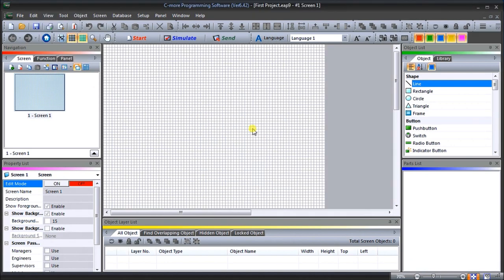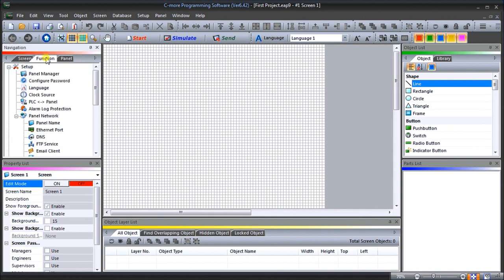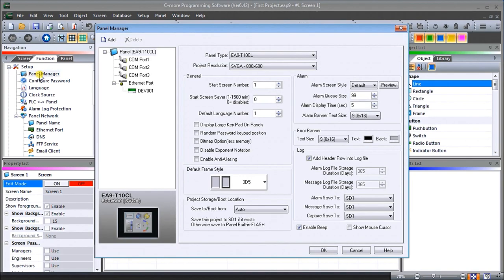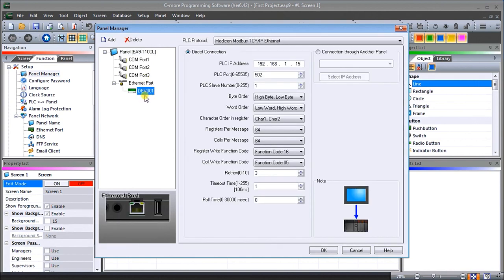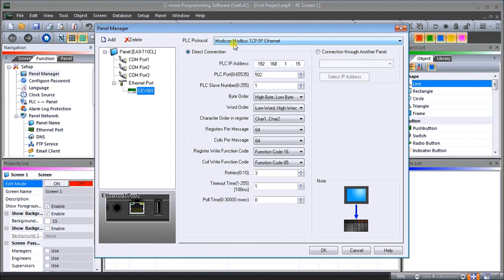Last time we looked at the communication. If we look under the Function of our Navigation and look at the Panel Manager, you'll notice we have the panel type EA9 T10 CL. If we look at the Ethernet port, we have a driver here DEV001 and it has the PLC IP address of 192.168.1.15 and Modbus TCP also uses port 502. Our protocol is Modbus Modicon Modbus TCP IP Ethernet. That's my communication functions.